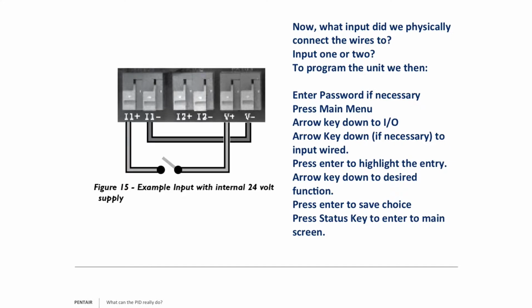We will then hit enter and then the arrow key up or down until we get to the input that we want to program. So for example, here we're hooked up to 1, so we go to input 1. Then press enter to highlight the box, because it probably says unused at the moment, and we're going to then decide, do we want it to run, fault, or run at a different pressure. Once we decide that, hit enter to lock it in. Now once you have that, I always hit the status key, which is the button on the bottom right, which takes me out of the menu and brings me back to the main panel that we're normally accustomed to seeing, and I would hit auto start and then test to see that I programmed it properly.